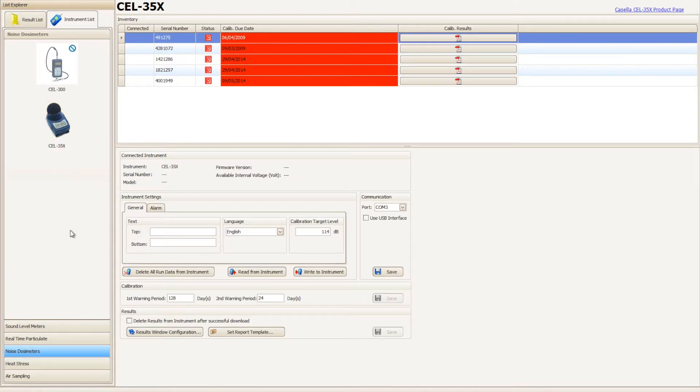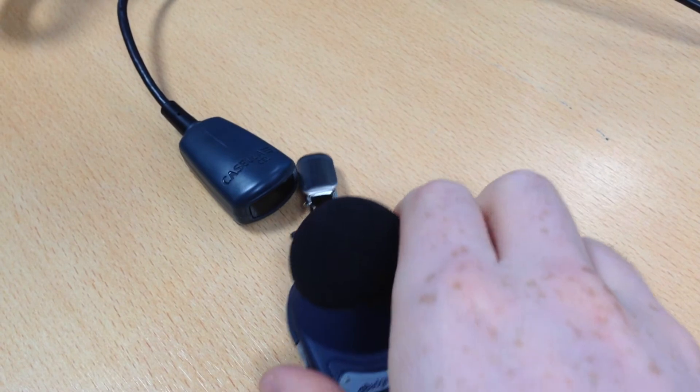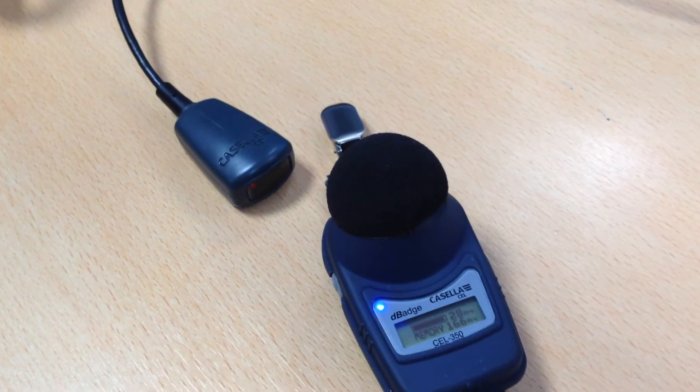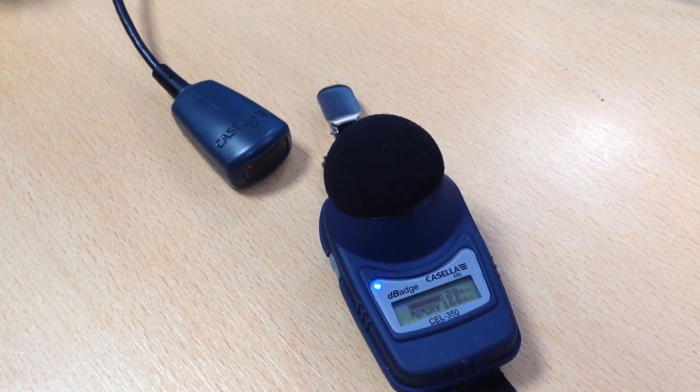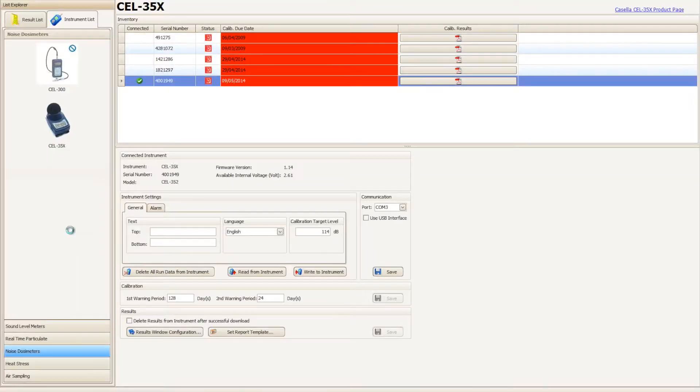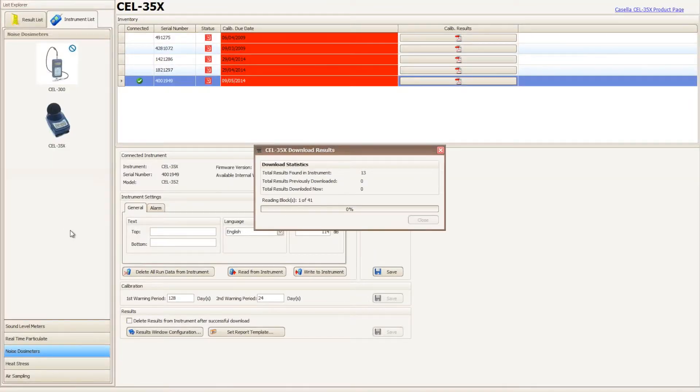Power your Casella 35X D-Badge on and place it in front of the infrared dongle. A blinking blue light will confirm a successful connection. Casella Insight will now automatically initiate a download of the runs within the instrument.